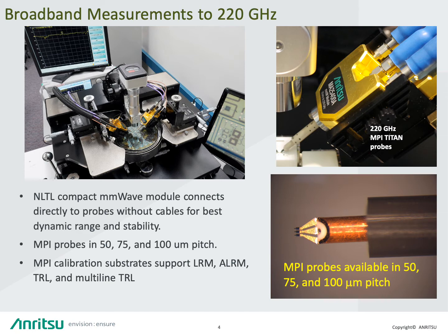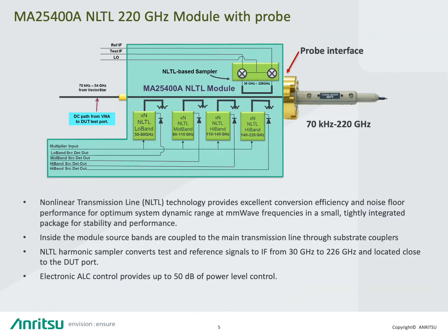50, 75, and 100 micron pitch. MPI also offers calibration substrates that support a wide range of calibration capabilities. The 220 gigahertz module provides a DC path back to the VectorStar baseband VNA.